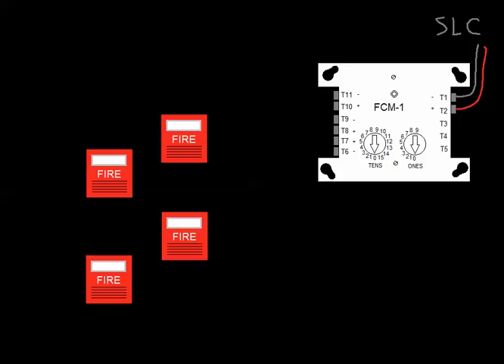So in the top right, connected to the module terminals T1 and T2, that's the data circuit or the SLC. That would be connected in some form back to the panel on the SLC terminals, but more commonly it's going to be tied into another device because you can imagine there's going to be several devices on that loop.